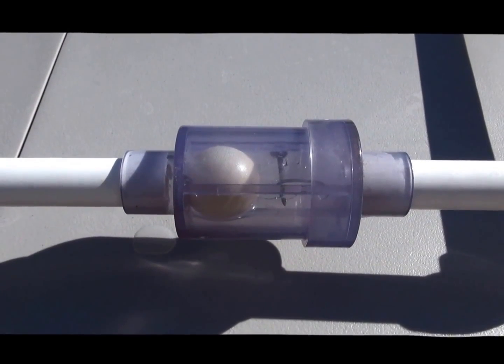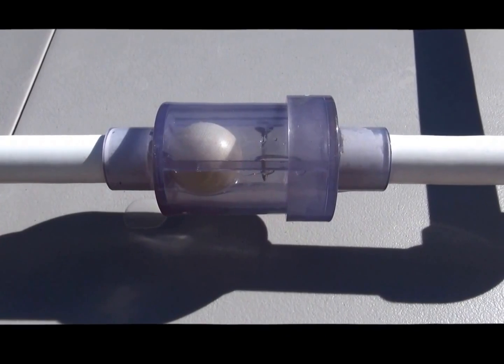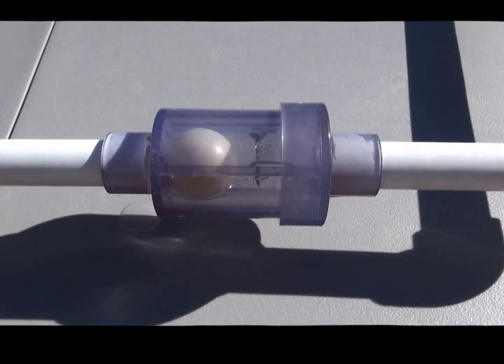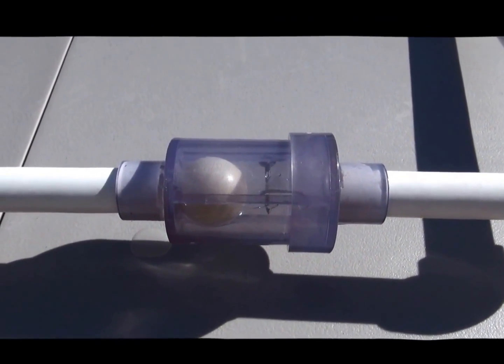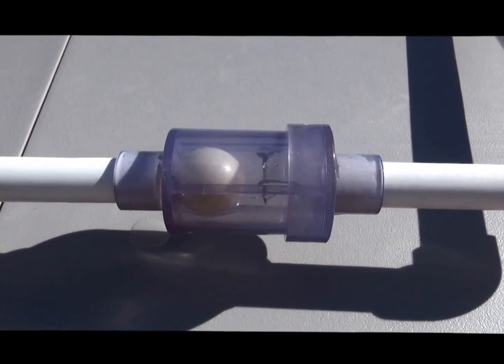But you're leaking probably 0.1% of the air that would normally go through a dry trap, 0.1% or less. You can't feel any suction at the end of the drain line with your hand.